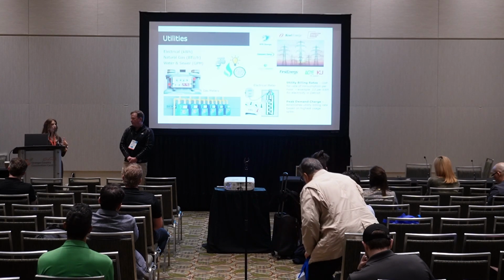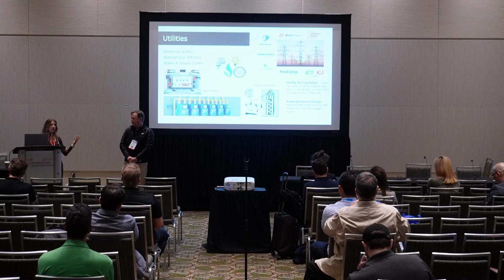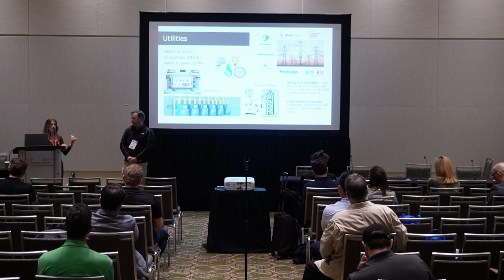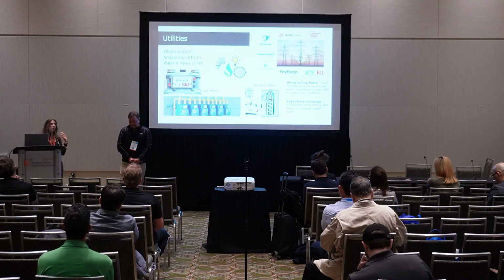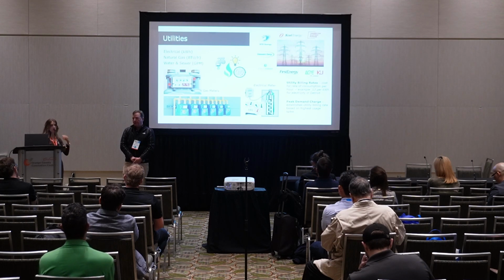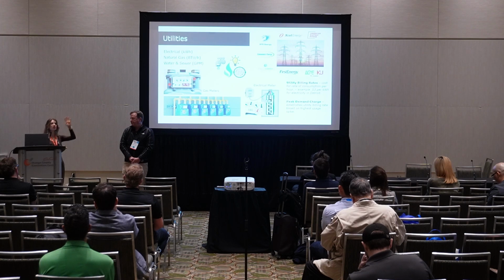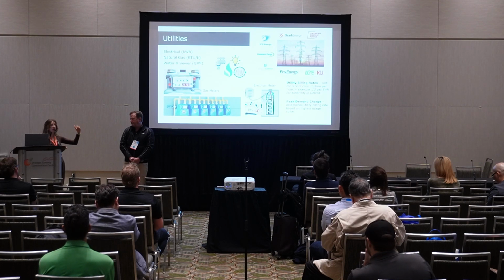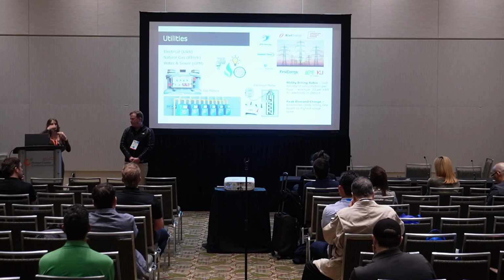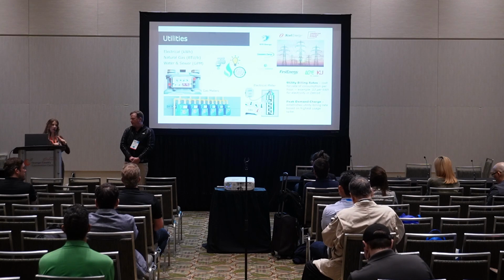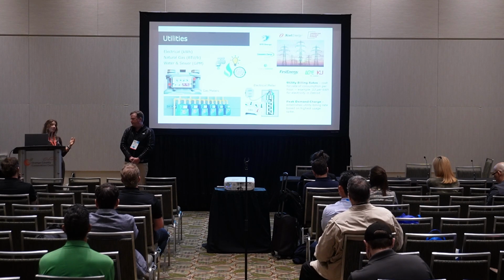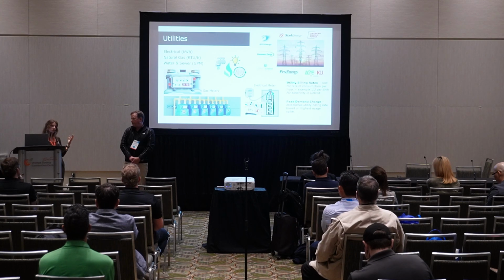You can do that if you had a bunch of air conditioners in a building - stagger them so they can't all turn on at once. The ones farthest from set point turn on first, and once they're within 2 degrees, they turn off and let the next ones turn on. You stagger the load so you're not getting it all at the exact same time, and that saves a lot because peak demand charges can be really significant with a lot of electrical load.